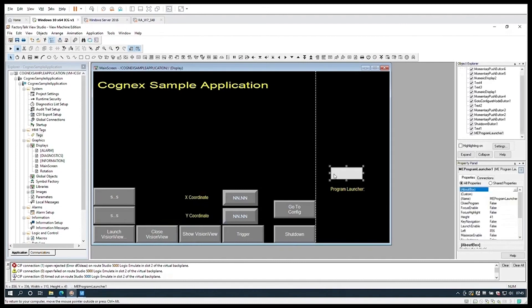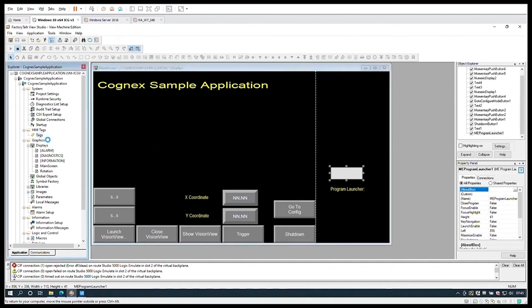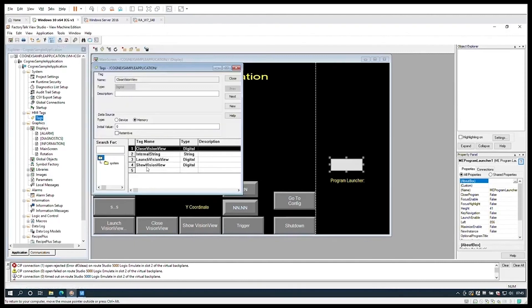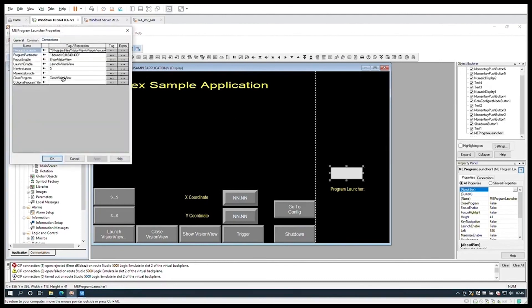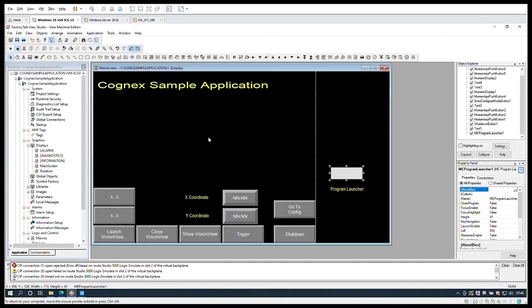Let's look at one we've already set up, starting with the tags that the Program Launcher will use in the HMI tags, which we see again used in the Program Launcher ActiveX. We have the Program Location for the executable file. The bounds determine where in the XY coordinate on screen it appears and its size. The focus brings it to the front. The launch starts the application, while new instance set to zero makes sure we don't open it twice. You also have the option to close VisionView, and you could use Macros to trigger the tags when opening or closing the screen.